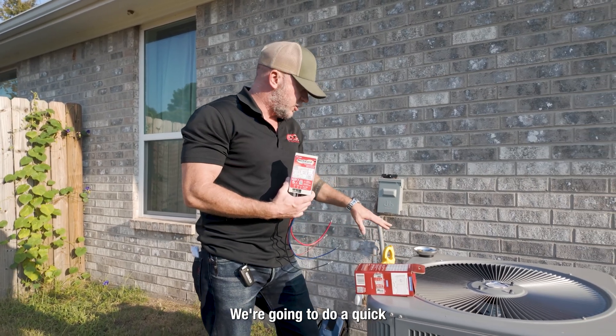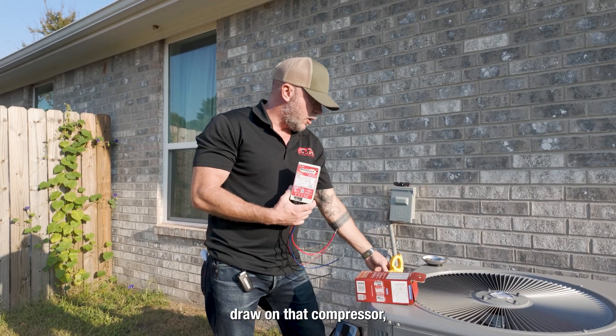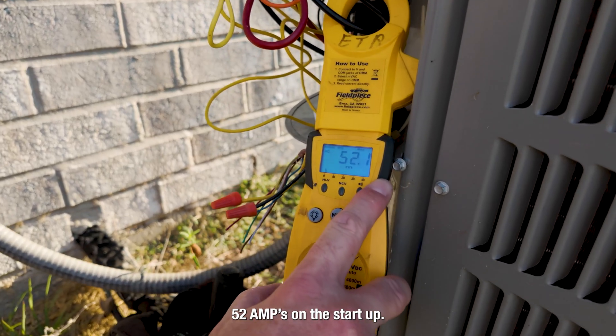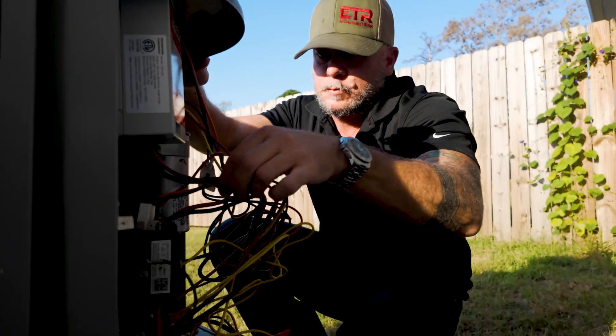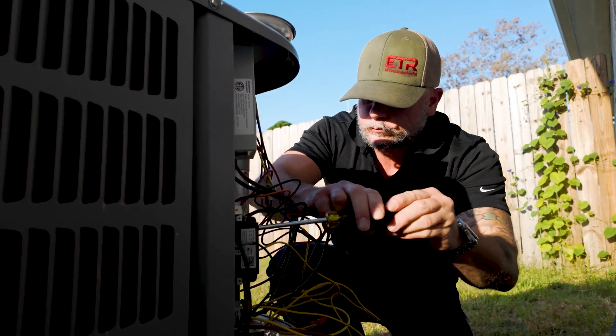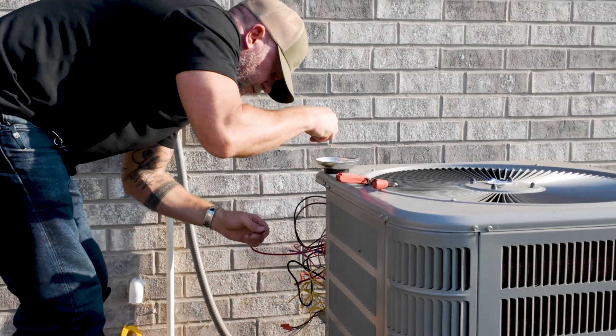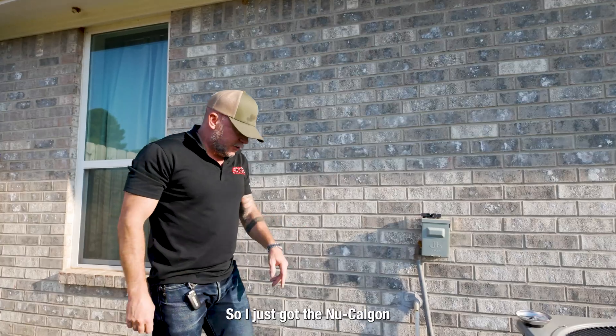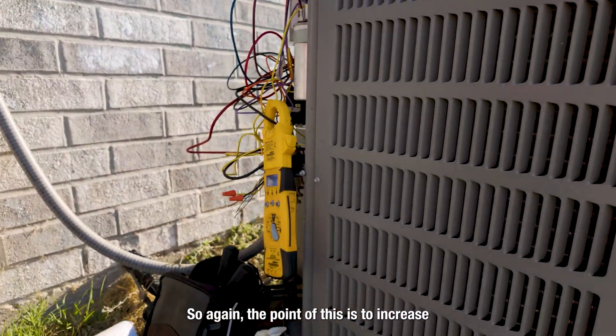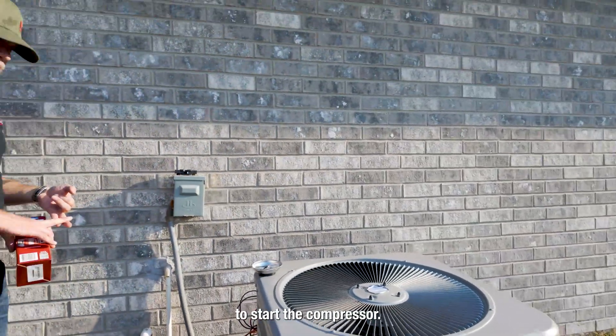We're going to do a quick startup on this without the soft start and I'll show you the amp draw on that compressor, and then we'll do it again after I get this installed. I just got the Nu-Calgon soft start installed. The point of this is to increase the compressor life and lower the amount of power required to start the compressor.